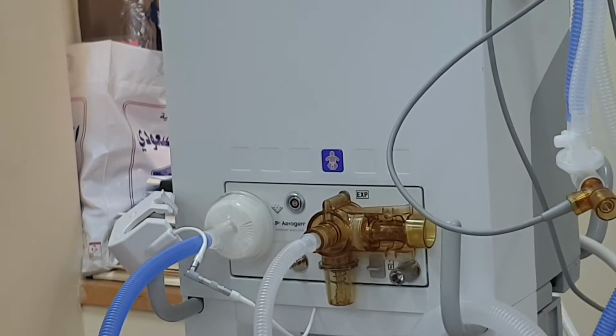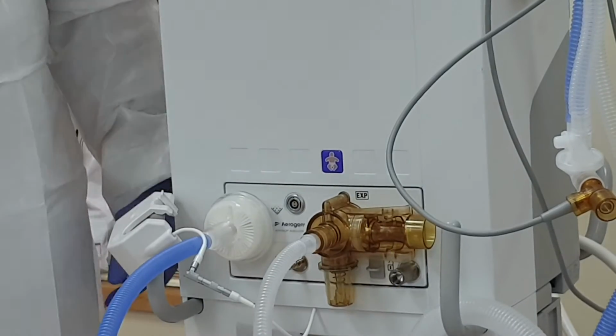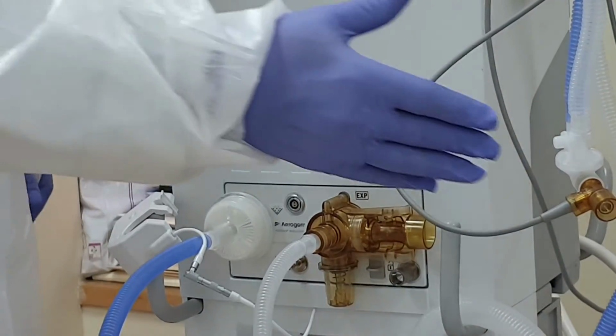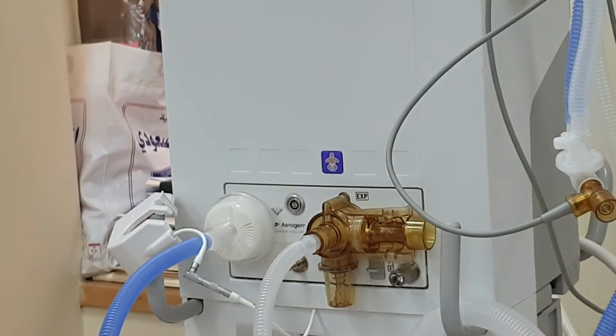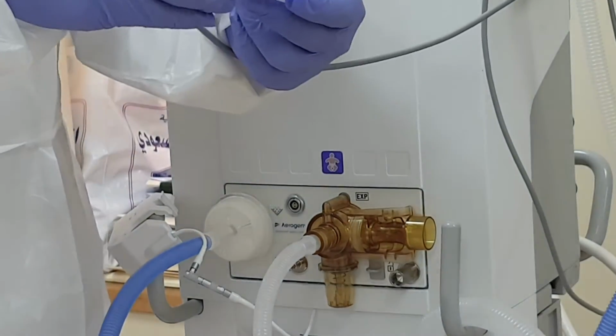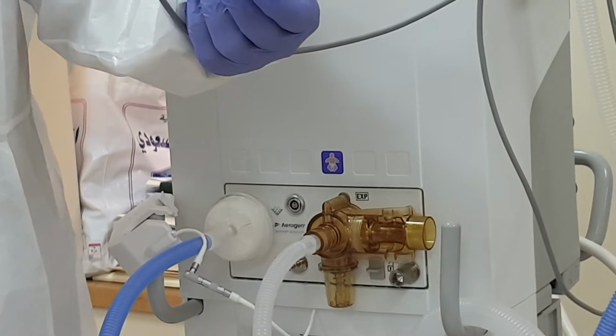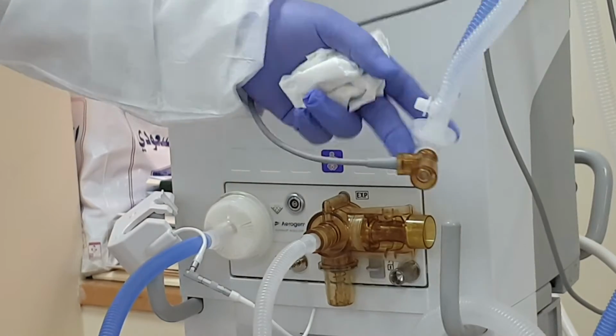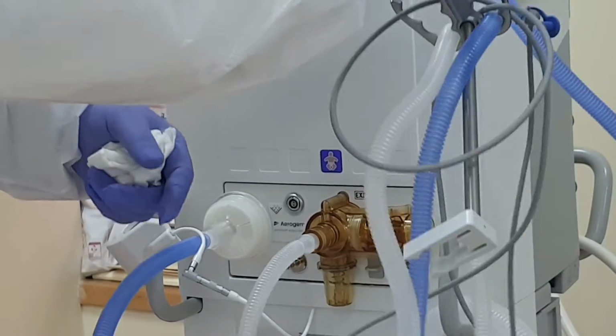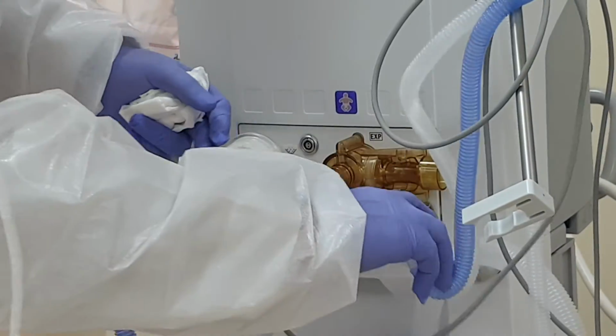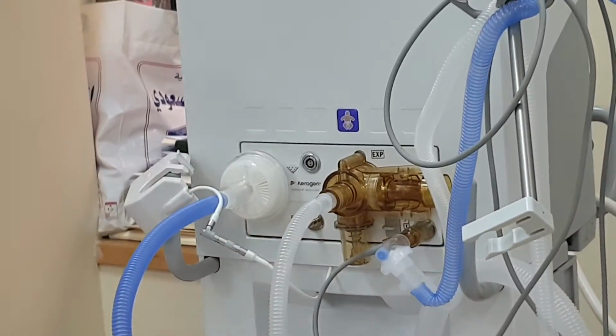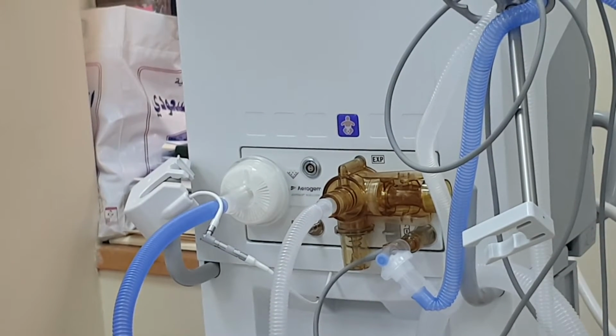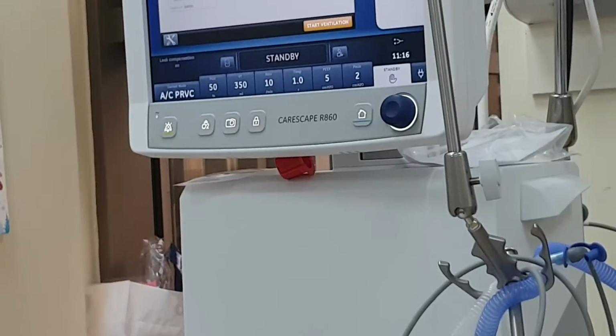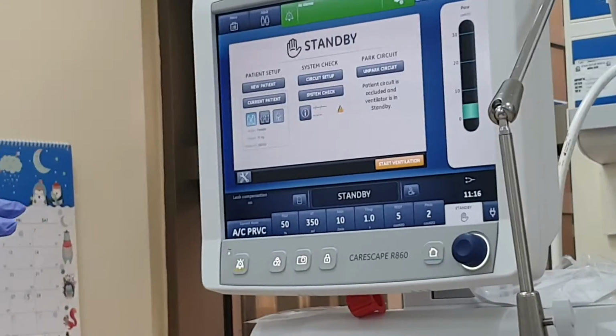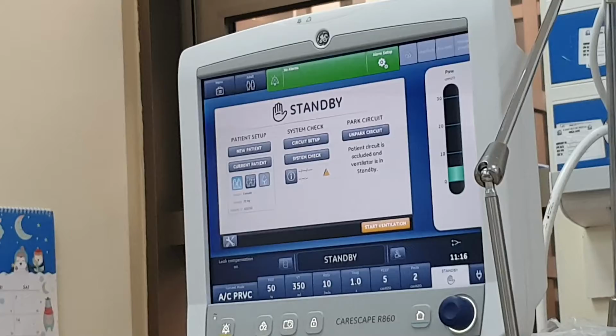Okay, then we do have this part, which is just to park the circuit. So if you didn't have a cap, or for example this cap cannot be put in over here because of the flow sensor. Now we are using the flow sensor, we cannot put the cap. So what we do, you don't need this one. You just take the whole thing down and try to connect it over here. Now it's on park. Now it tells you that patient is detected, but in reality it's not connected to the patient. So what you do, you park the circuit, and now we are telling the machine that we did not connect the patient, just in a park position.